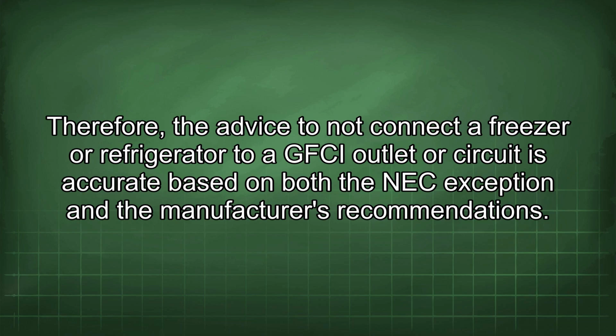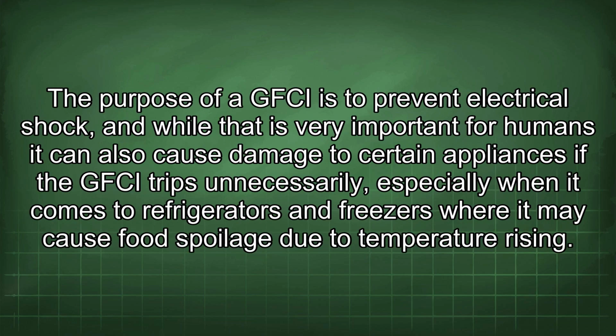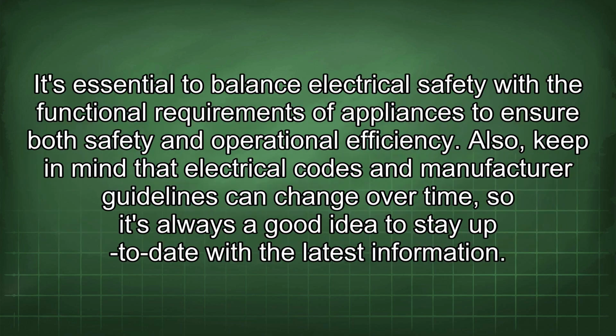Therefore, the advice to not connect a freezer or refrigerator to a GFCI outlet or circuit is accurate based on both the NEC exception and the manufacturer's recommendations. The purpose of a GFCI is to prevent electrical shock, and while that is very important for humans, it can also cause damage to certain appliances if the GFCI trips unnecessarily, especially when it comes to refrigerators and freezers where it may cause food spoilage due to temperature rising. It's essential to balance electrical safety with the functional requirements of appliances to ensure both safety and operational efficiency.